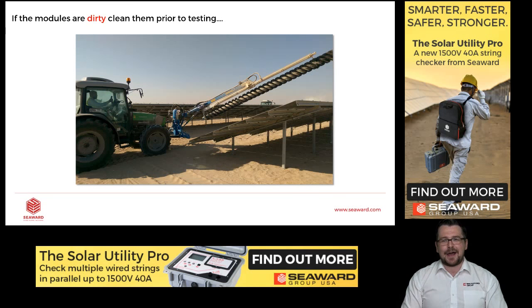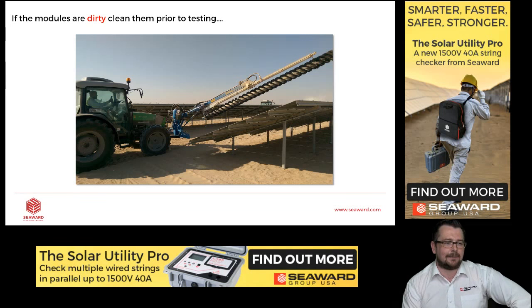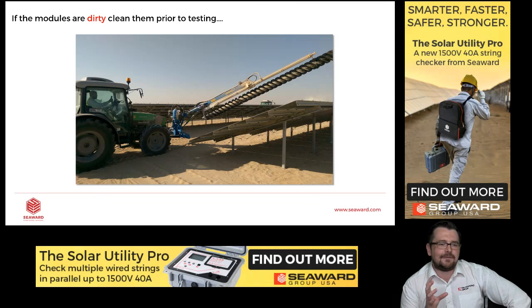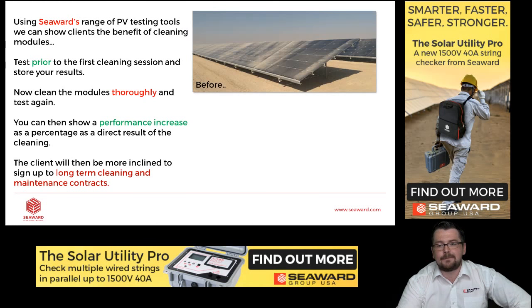Here's the picture I mentioned earlier. It's in the wrong order, so apologies for that. But this is the big JCB machine that was kicking up the stones and breaking the panels. But I think this particular slide really does highlight that if during your visual inspection you see that the panels are dirty, you really should clean them prior to testing. Okay, make sure that you clean them and that we're testing from a clean array. And there are some really good reasons for doing that.